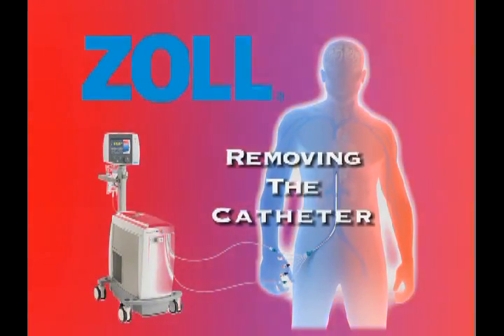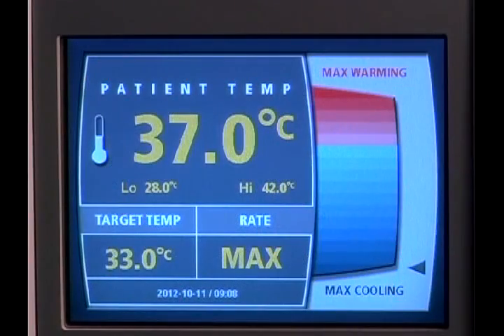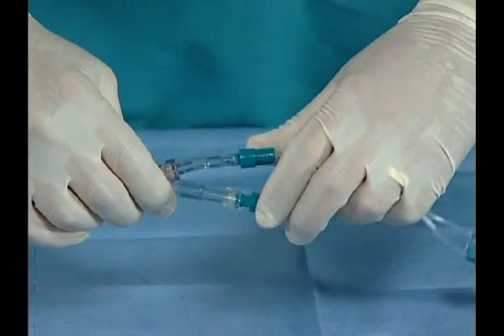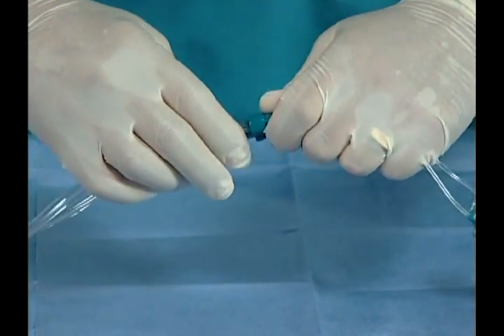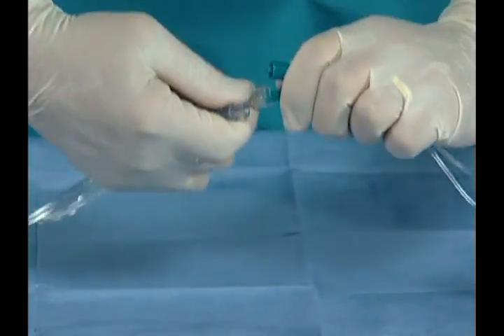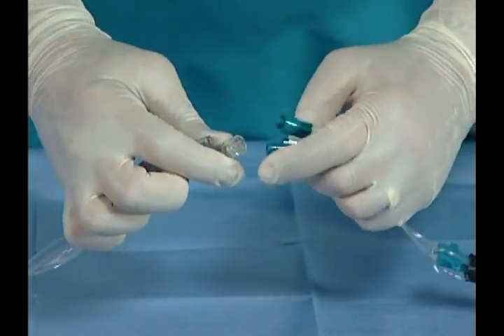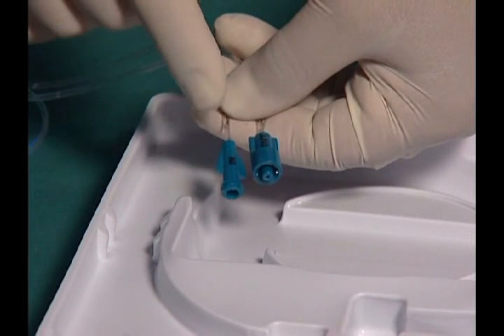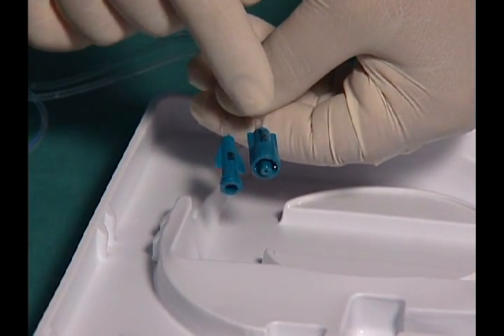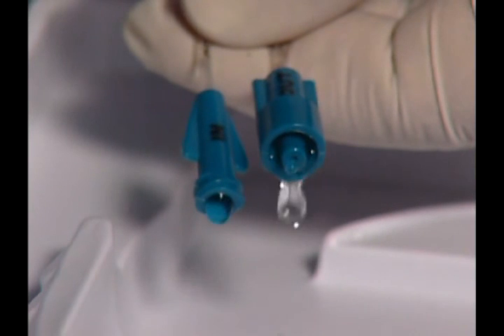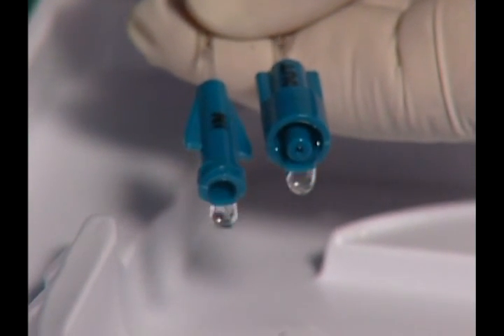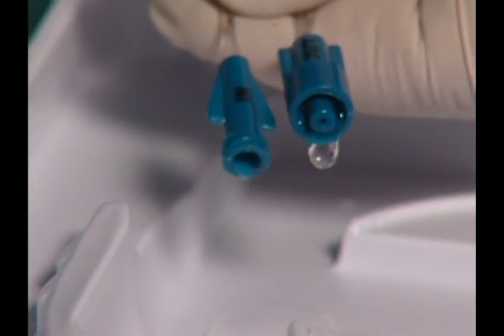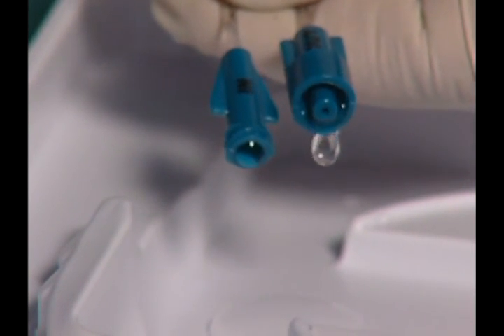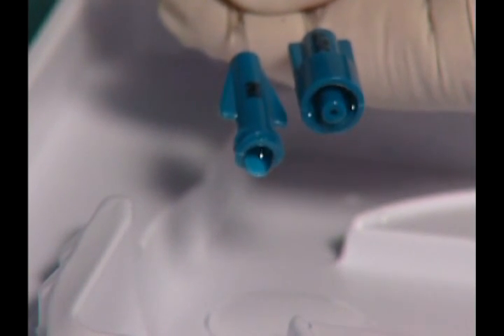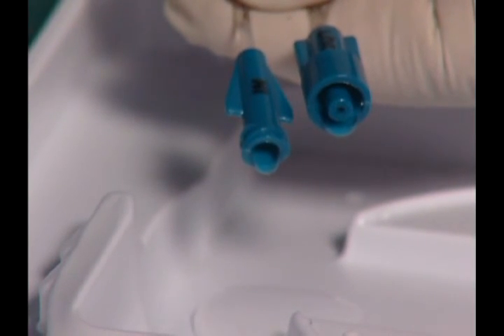Removing the catheter. To remove the catheter, first place the system in standby mode. Then, disconnect the startup kit tubing from the catheter. Do not cap or cross-connect the catheter saline inflow and outflow ports. Both the inflow and outflow saline lumens must be open so that the saline can freely flow out of the balloons during the extraction procedure. This is important because the balloons must be able to fully deflate in order to facilitate easy removal from the vessel.